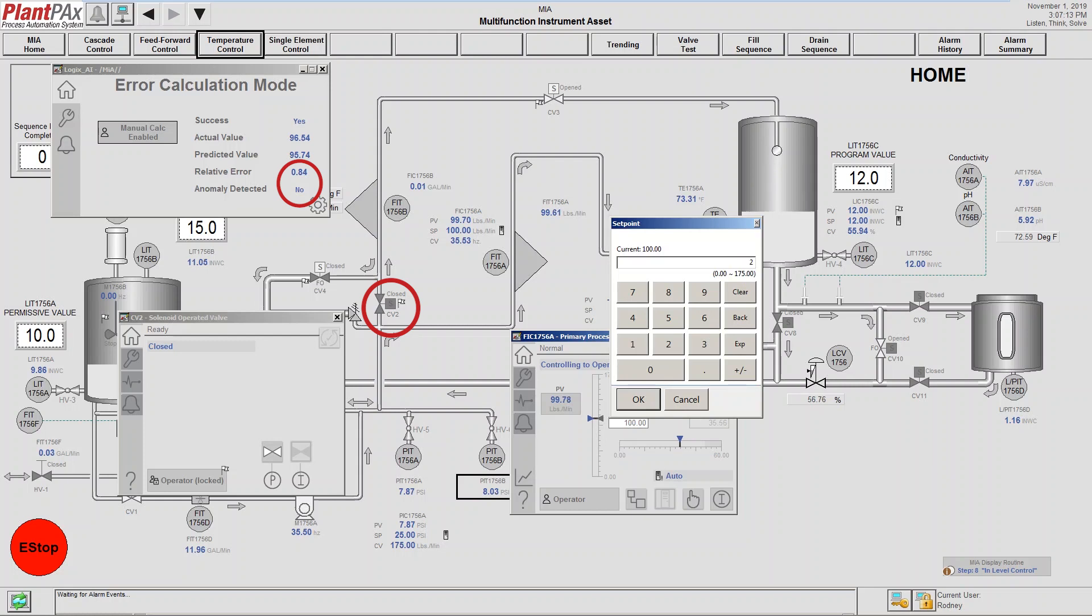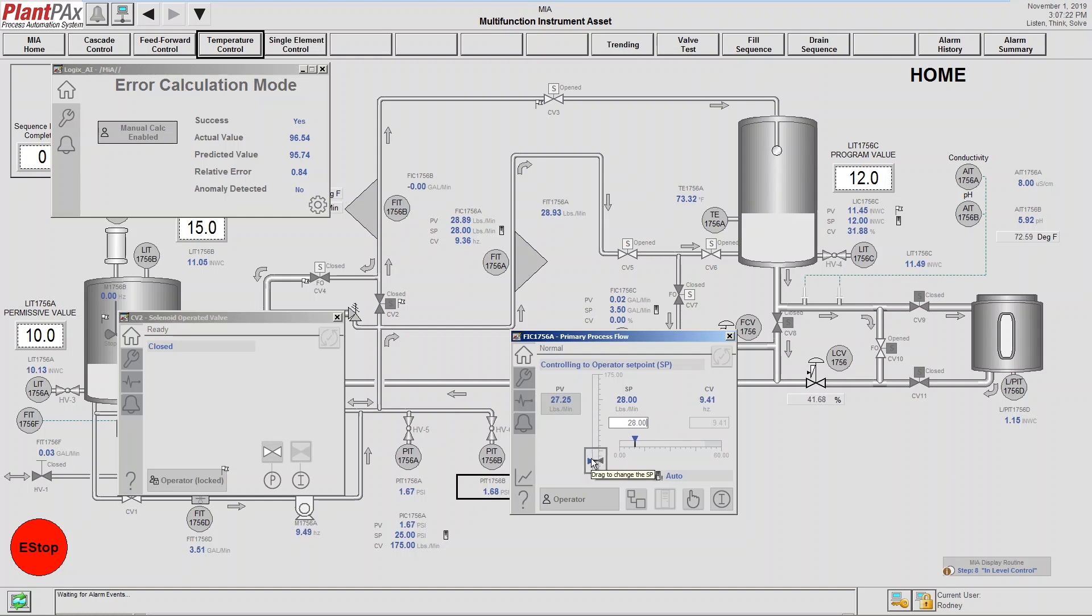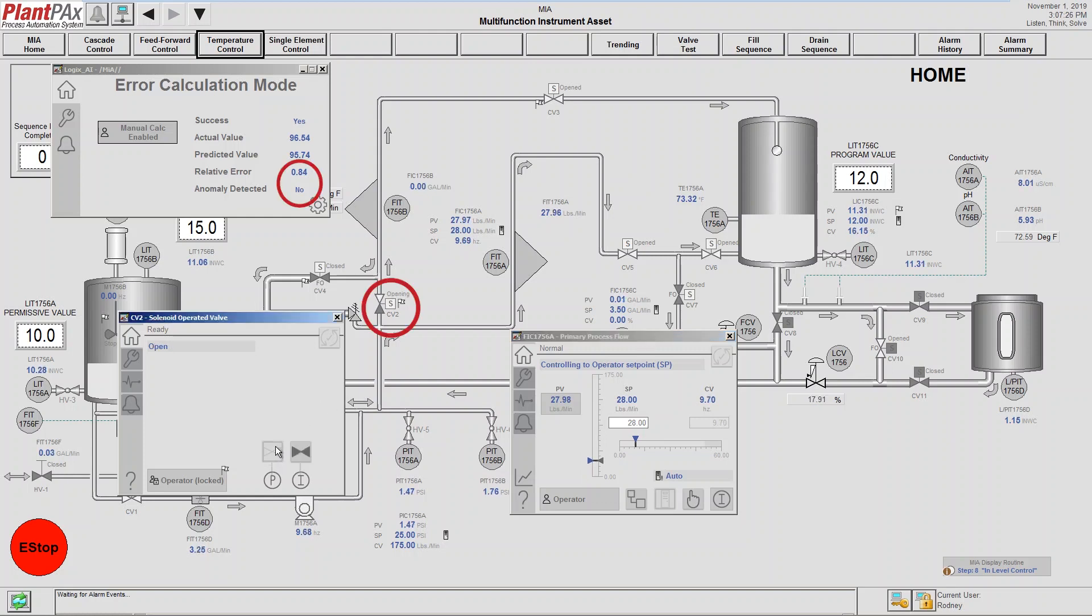The next step is to test how low can we go on the flow before we actually trigger the anomaly. So we've now set the flow rate at 28 pounds per minute. Again, we're going to open the bypass valve flowing to the spray ball.